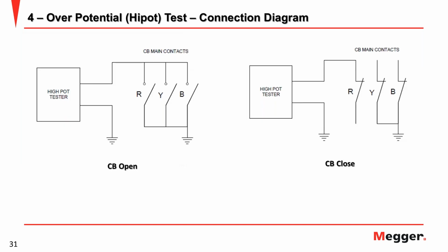And this is the connection, the same as the insulation resistance test, but be careful. This test, especially the AC test, can only be done after you get a pass value on the insulation resistance test. If you get a fail, it's not recommended to run this hipot test on the breaker. So after you get the pass indication from the insulation test, you can continue to this test.